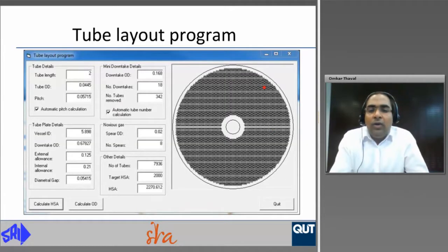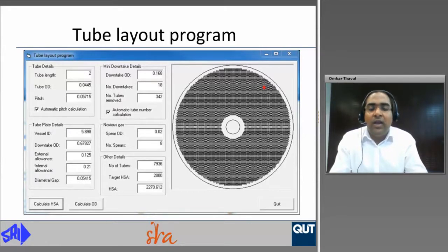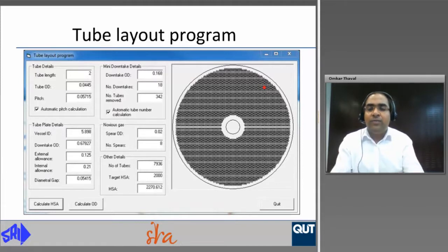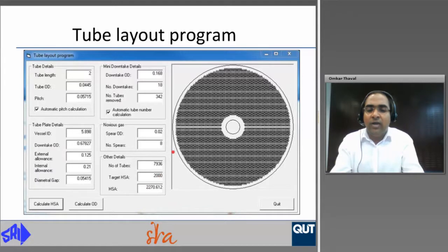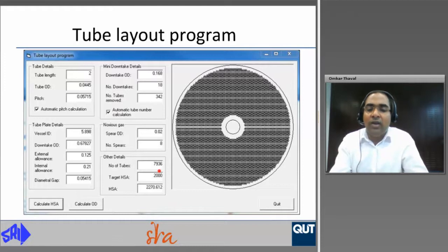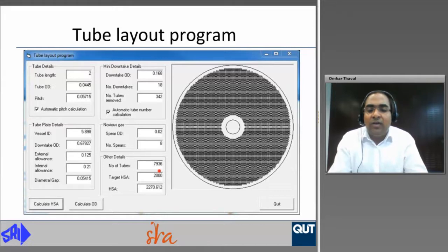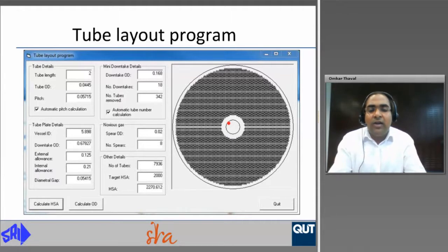A tube layout program developed at the Sugar Research Institute is used to determine the vessel diameter and number of tubes. The inputs are tube length, tube diameter, and the target heating surface area. The program calculates the vessel inner diameter and number of tubes for a given heating surface area and tube dimensions. All designs are based on the SRI type, which includes a central downtake of juice, steam annulus for radial inflow of steam, and mini downtakes.